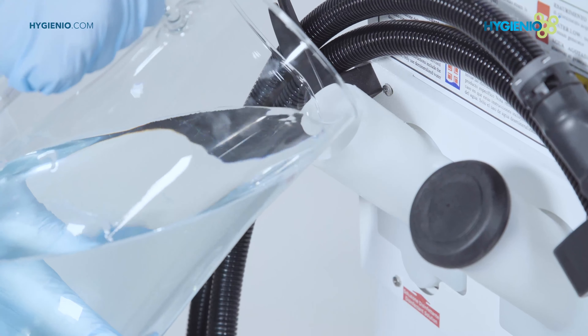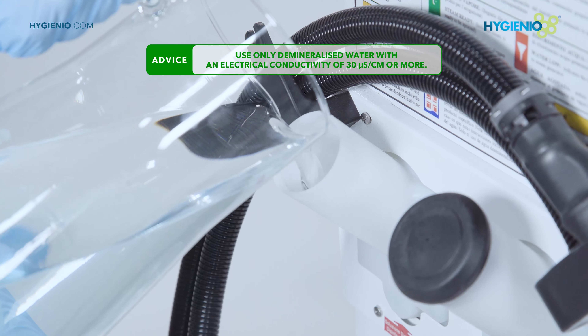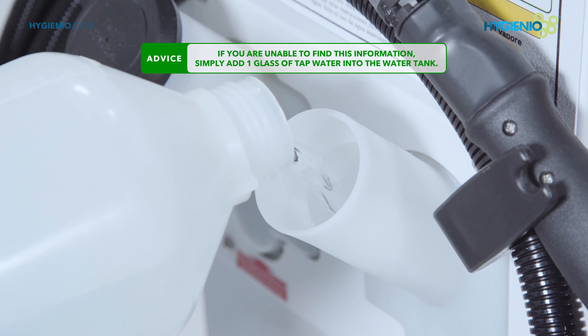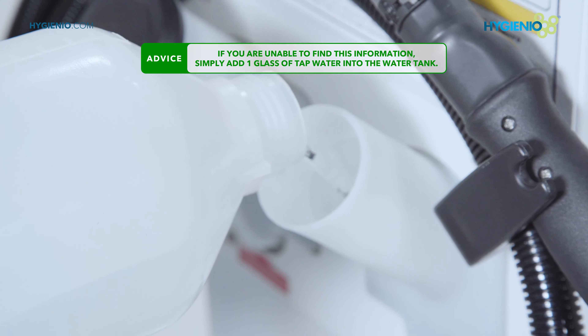Pour the prepared solution into the disinfectant tank. Fill the water tank with two liters of demineralized water that has an electrical conductivity of 30 microsiemens per centimeter or more.